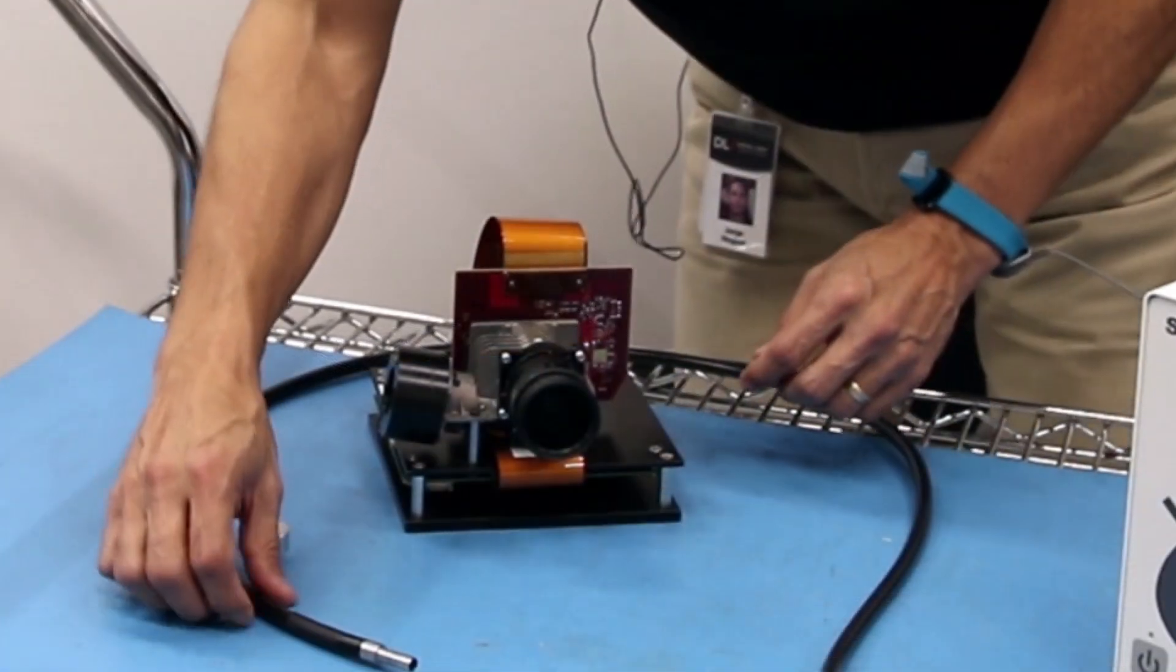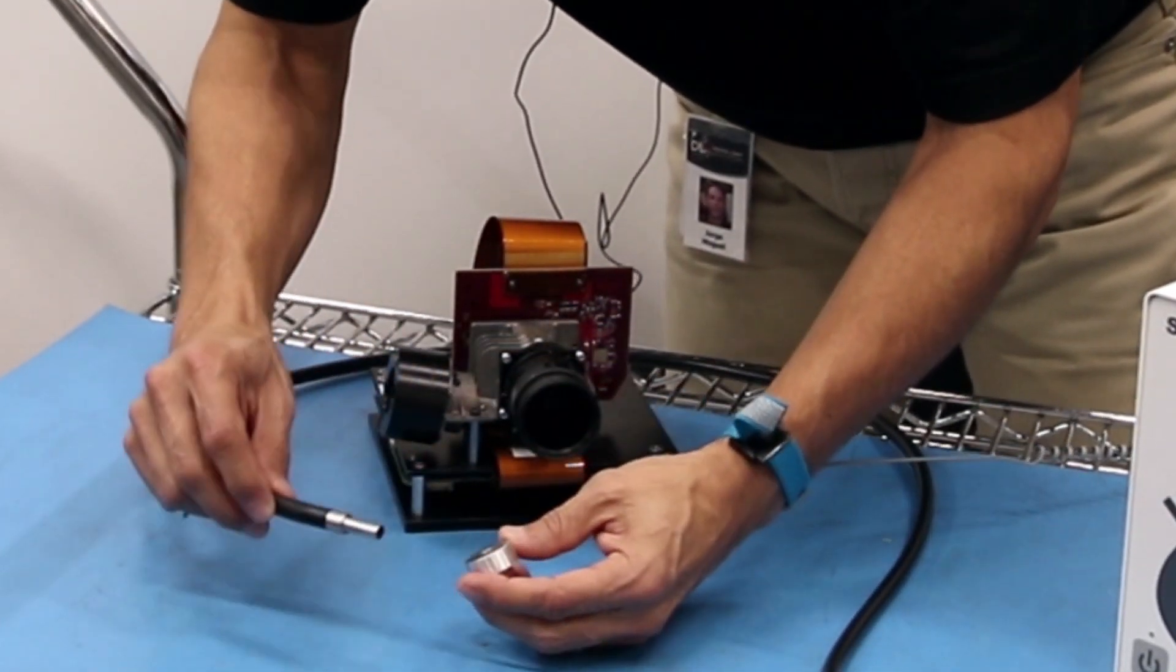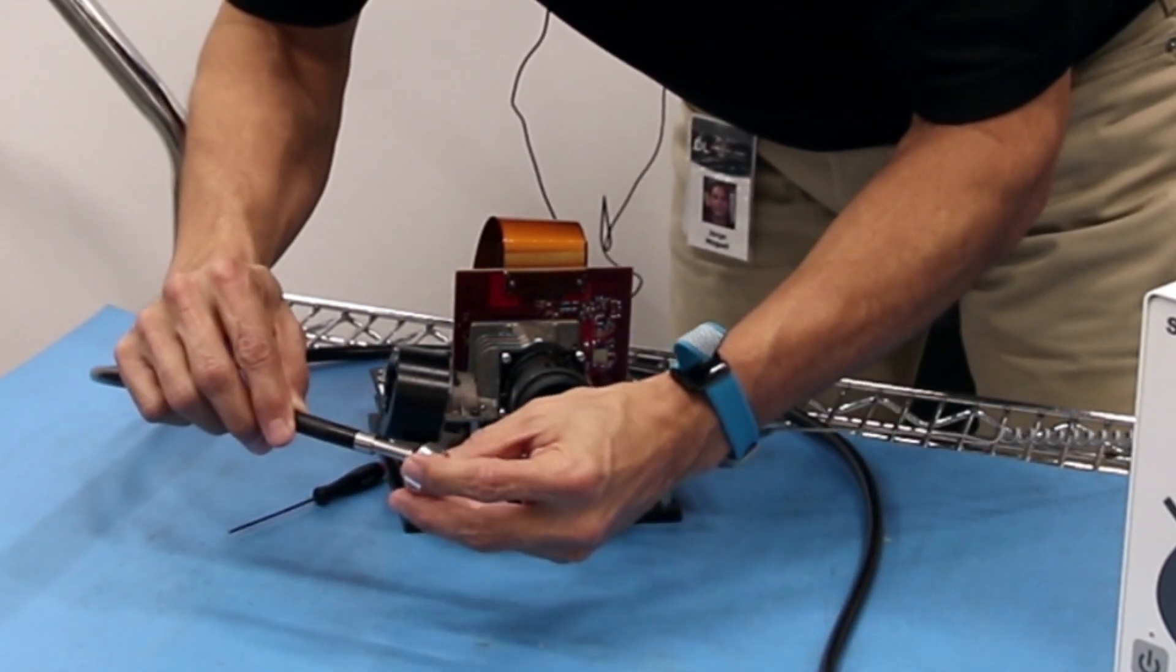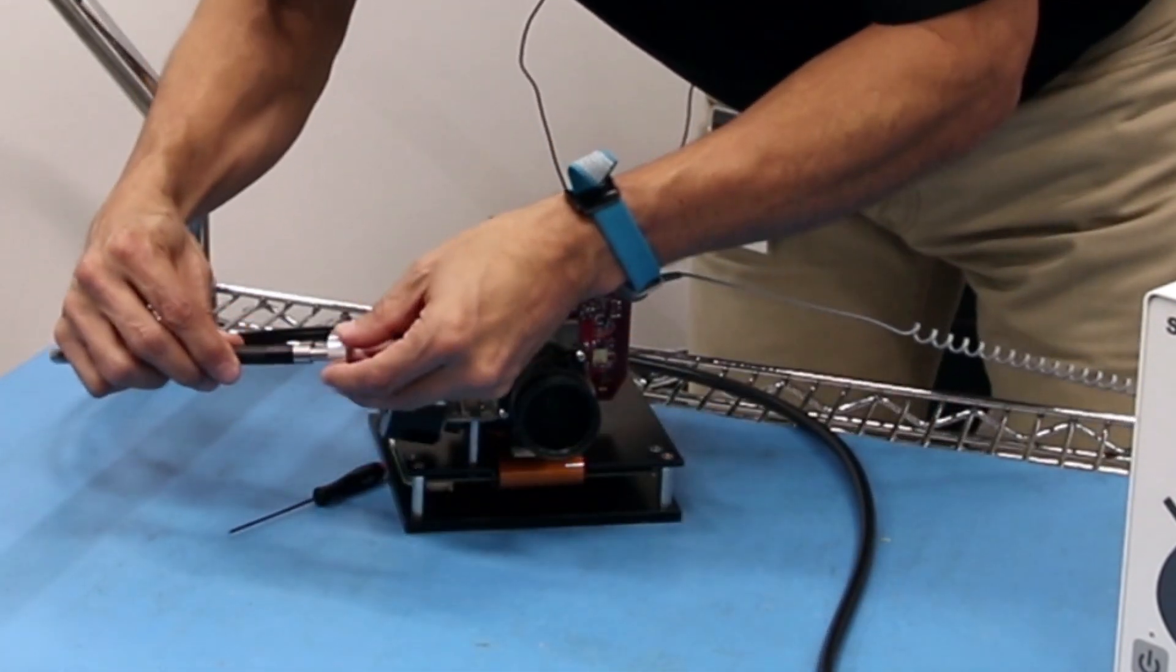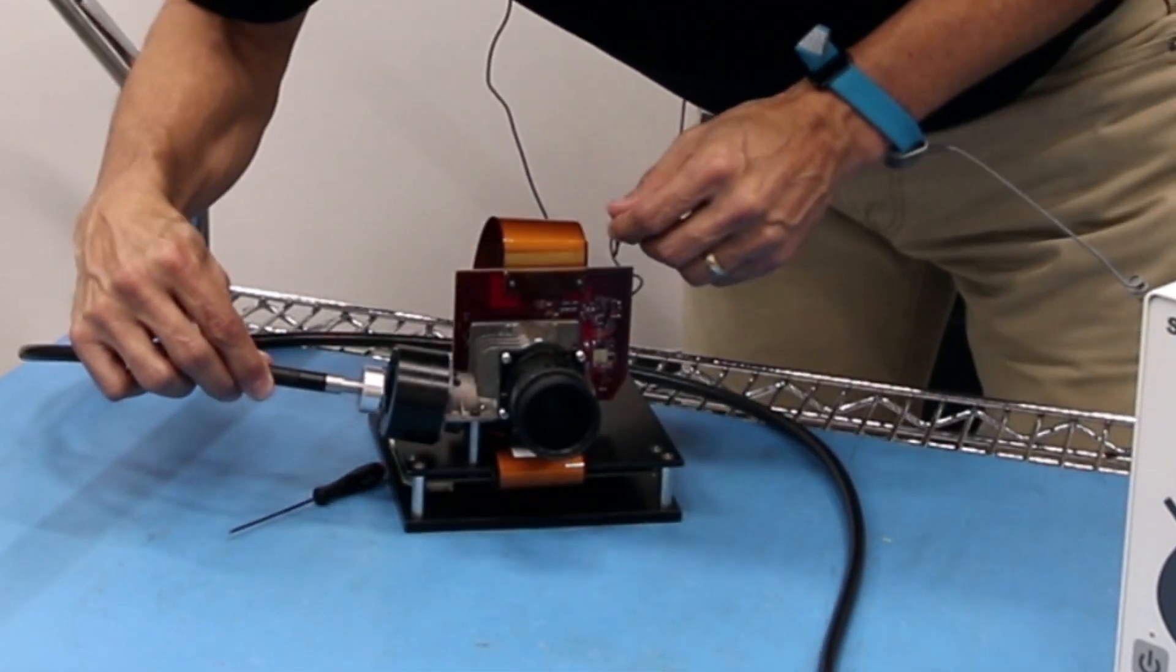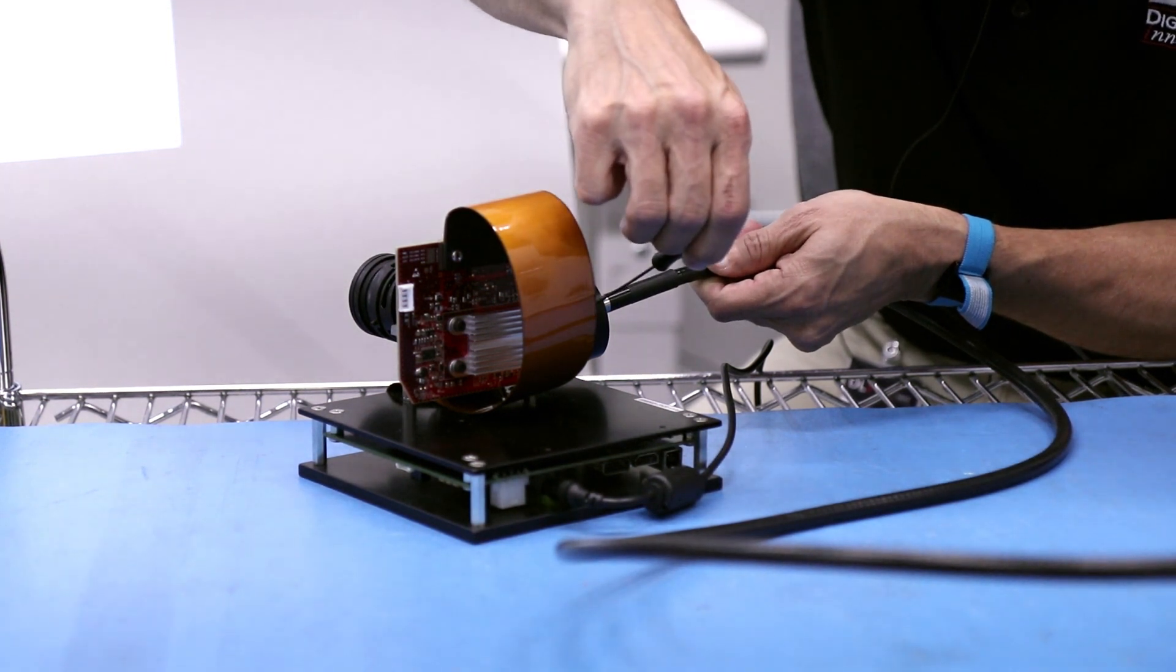Now that the fiber optic cable is in place we're going to implement similar steps on the optics bundle side. Take the loose end of the fiber optic cable and insert it into the ferrule adapter. Next insert the ferrule adapter into the fiber optic interface on the optics bundle. Use your 1.5 millimeter hex screwdriver to set the fiber in place.